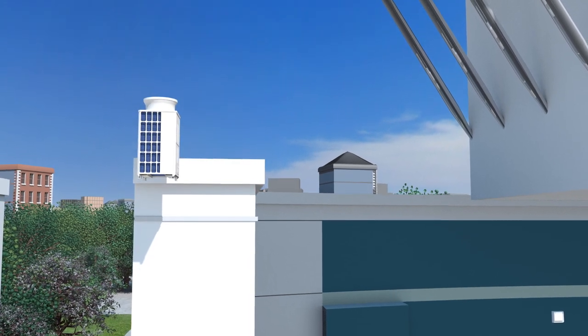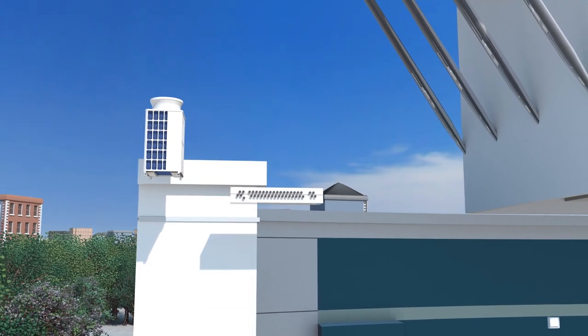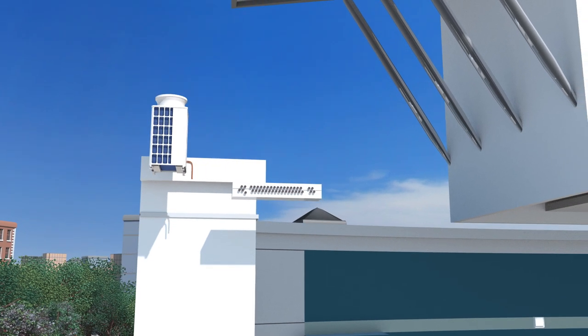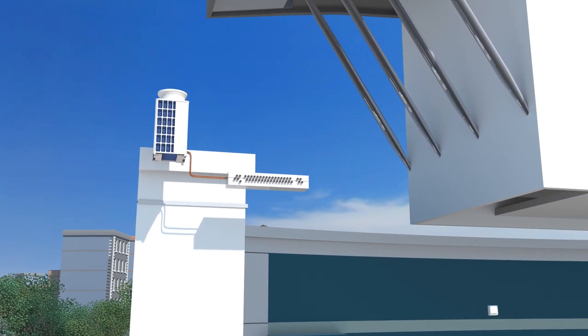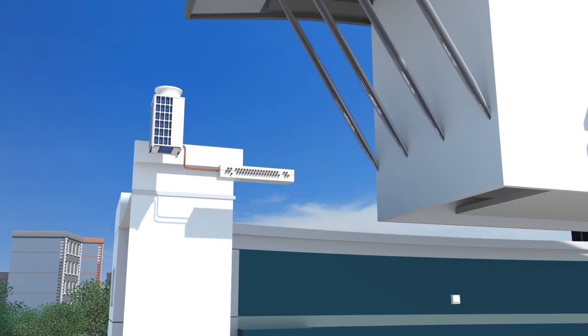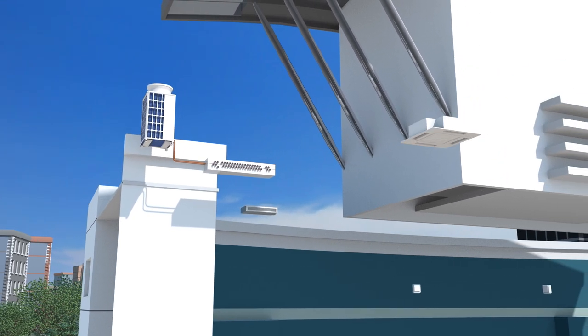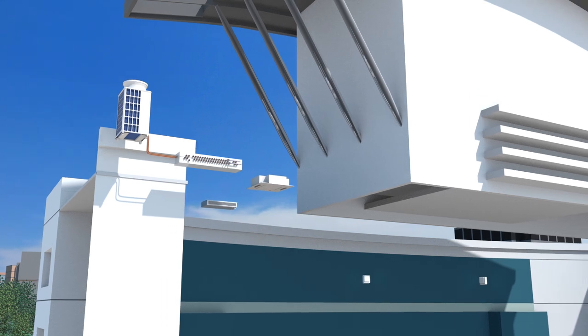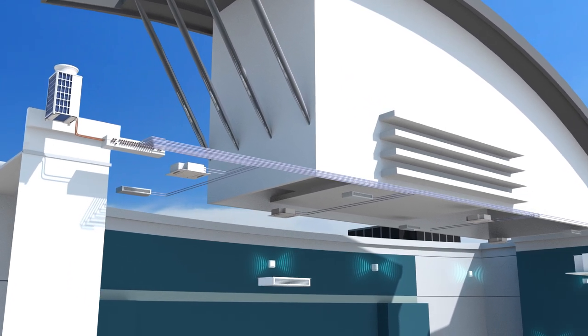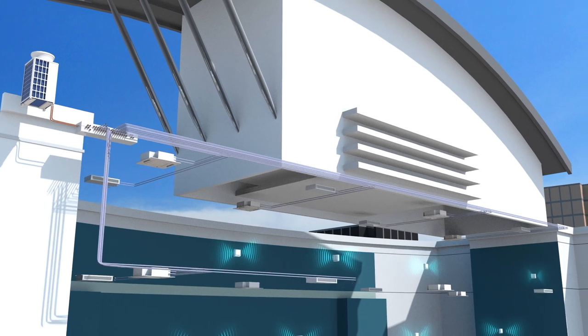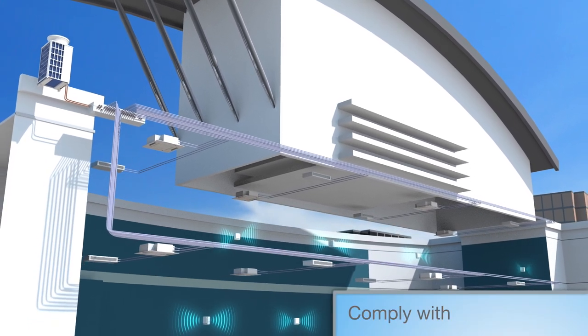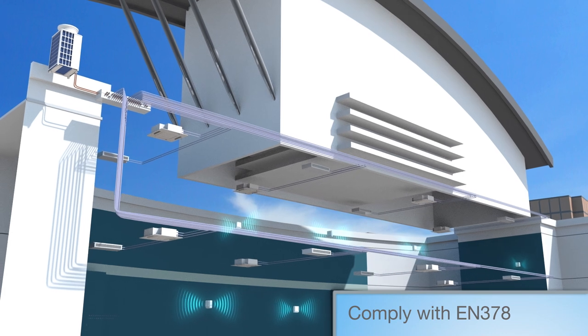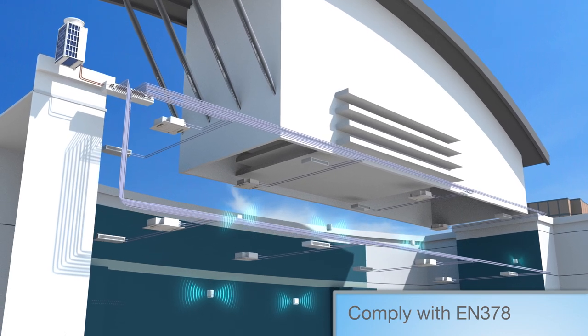The hybrid VRF system uses the same city multi-heat recovery outdoor units and these are connected to an HBC controller by refrigerant piping in the same way as a standard VRF.